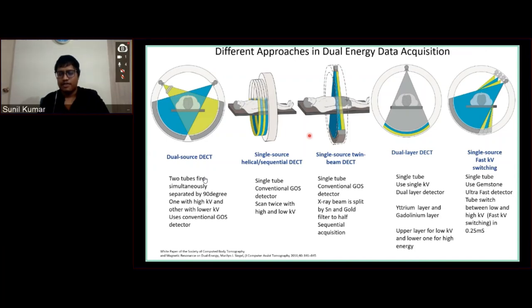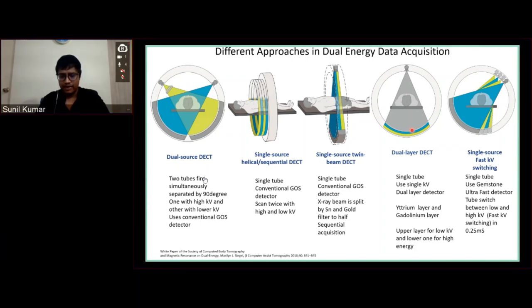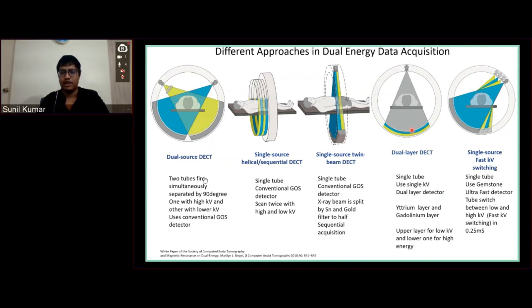We also have dual layer dual energy CT. Here they have a single source tube and have made changes in the detector — the detector has two layers, where the topmost layer is the scintillator and the bottom is the other layer. In theory, the lower energy — the 80 kVp-based energies — will be attenuated at the topmost layer, and the higher kVp energy is attenuated at the bottom layer. This is highly challenging, but it is one of the techniques available in the market.